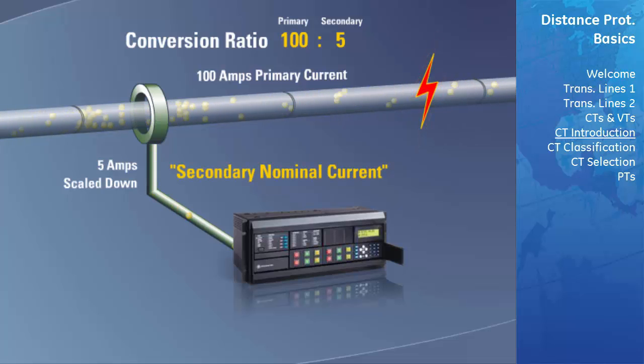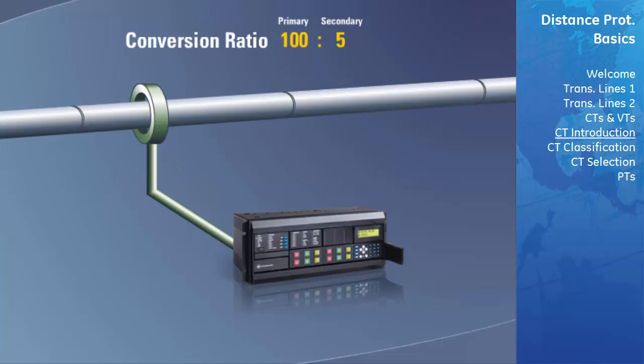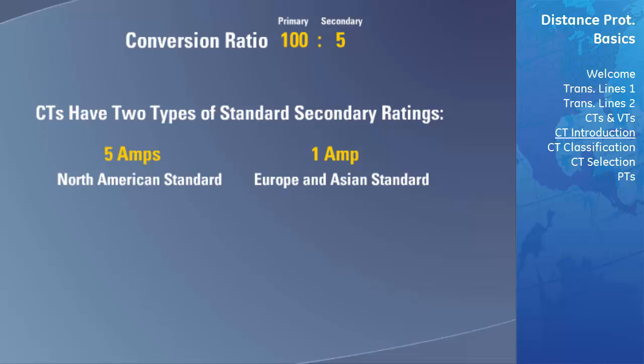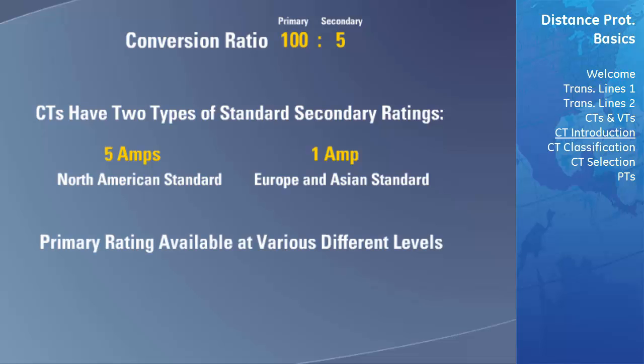If a fault were to occur on this phase that increases the primary current to 200 amps, then 10 amps would be passed to the relay through the secondary windings, consistent with the ratio. CTs have two types of secondary ratings: 5 amps and 1 amp respectively. 5 amps is typically the North American standard, while 1 amp is used in Europe and Asia. Primary ratings are available in various different levels, for example 100, 150, 200, etc.